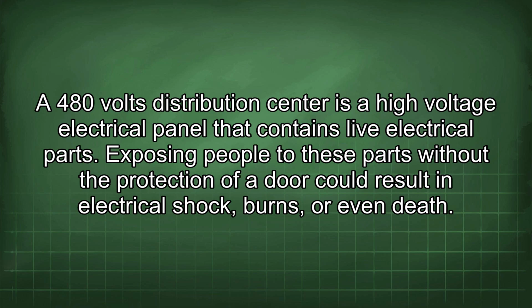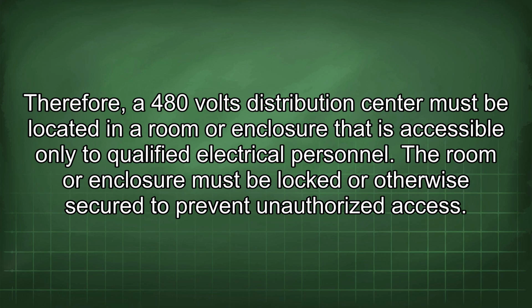A 480 volts distribution center is a high-voltage electrical panel that contains live electrical parts. Exposing people to these parts without the protection of a door could result in electrical shock, burns, or even death. Therefore, a 480 volts distribution center must be located in a room or enclosure that is accessible only to qualified electrical personnel. The room or enclosure must be locked or otherwise secured to prevent unauthorized access.